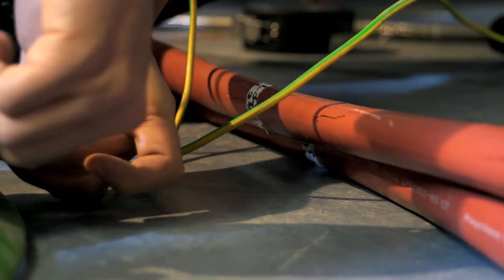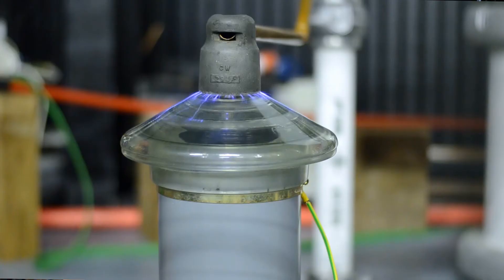Standard research tests can also be useful to investigate real network components such as this cable. When the localised region of the insulation is momentarily breached, a partial discharge occurs. This generates RF signals which can be used to identify where the weakness is, what it might be and its impact on the future performance of the cable.